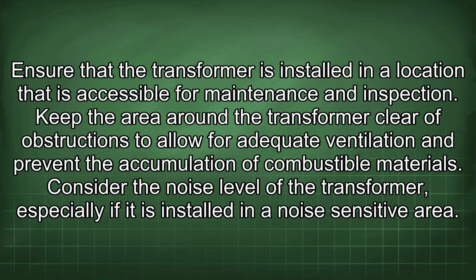Ensure that the transformer is installed in a location that is accessible for maintenance and inspection. Keep the area around the transformer clear of obstructions to allow for adequate ventilation and prevent the accumulation of combustible materials.